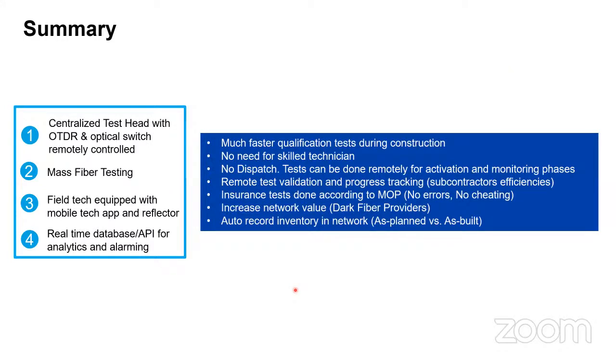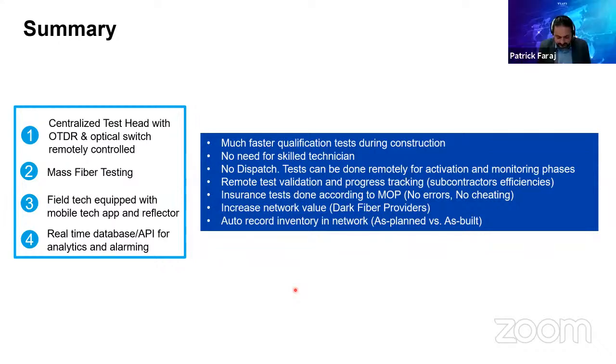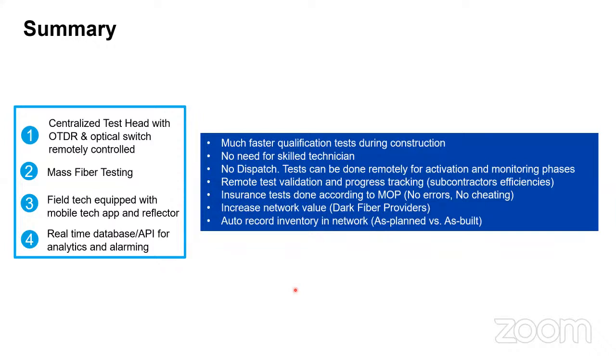Yes, in a sense, yes. It's the same OTDR you might use in a handheld. But this system is different, as Patrick mentioned. Essentially, instead of having the OTDR at the far end, normally you test from the feeder, from the drop cable, and then you test across the splitter. Here we place the OTDR in the central office. So first of all, there is only one OTDR, instead of many. So it requires an optical switch because you need to scan more fibers than just one.